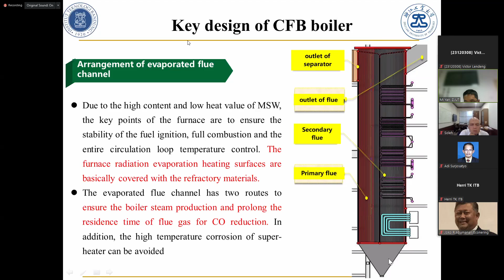About corrosion, the temperature at the inlet of the superheater should be lower than 700 to decrease the temperature of the tube wall. Of course, if it is lower than 700, your steam temperature, the superheated temperature, cannot be higher. So it is 450 centigrade usually. The material of the high temperature superheater is TP347H, and the steam temperature should be about or less than 450 centigrade. And the air preheater is in a hierarchical arrangement, with a porcelain lining. So this is the material, right? In the mill, just like crystal or glass type, it is used to prevent low temperature corrosion.